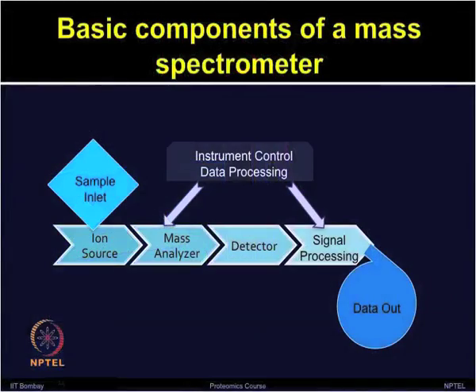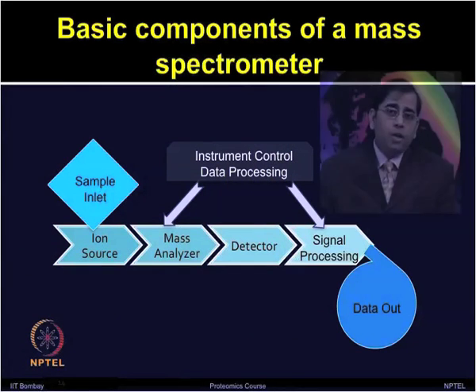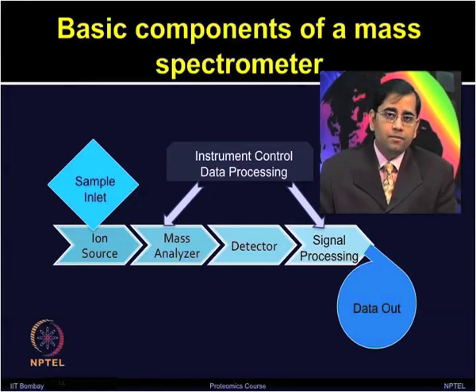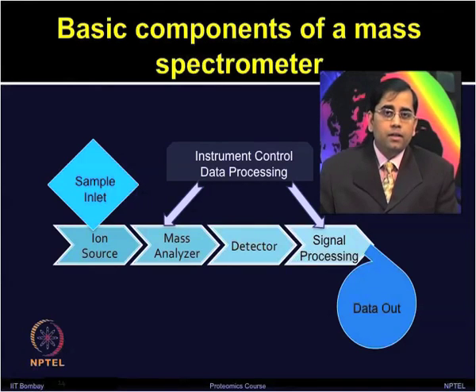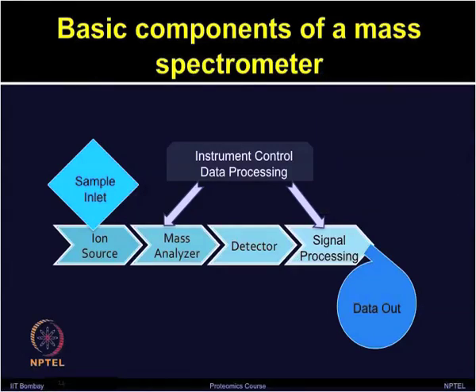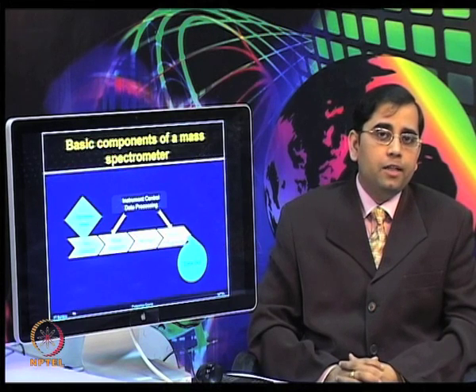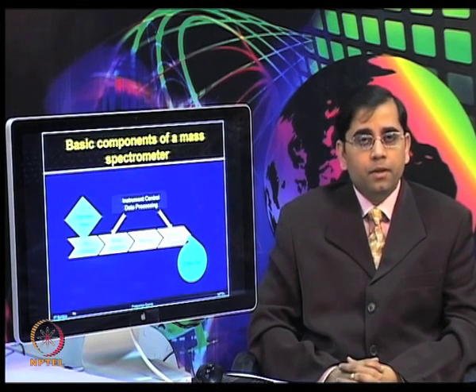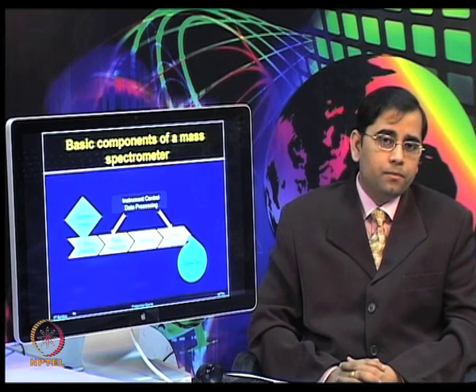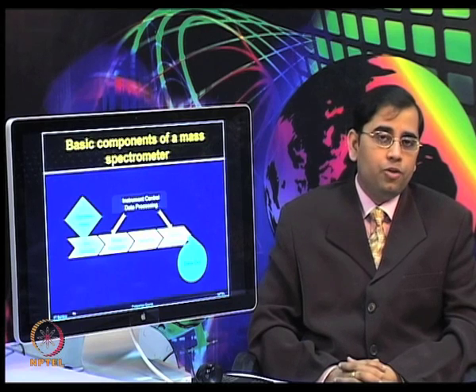The sample inlet transfers a sample into the ionization source. The ion source or ionization source converts neutral sample molecules into gas phase ions. The mass analyzer separates and analyzes the mass of ionic species. There are various types of mass analyzers, which we will discuss in more detail later. A very low vacuum pressure is maintained inside the mass spectrometer. The detector measures and amplifies the ion current of mass-resolved ions, and electronics are needed to control the operation of various units.